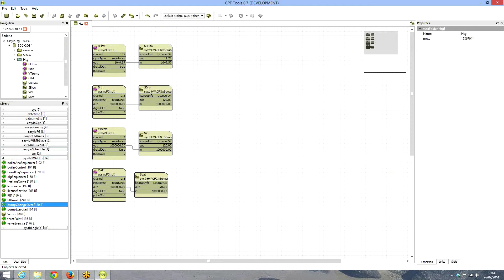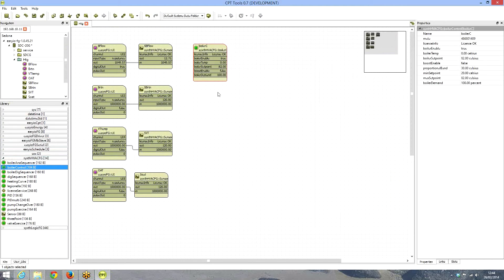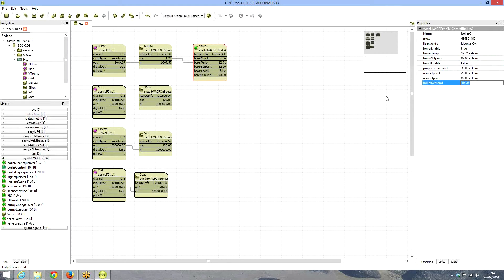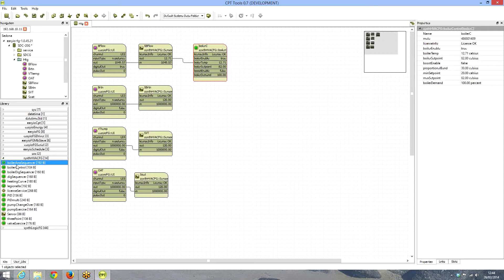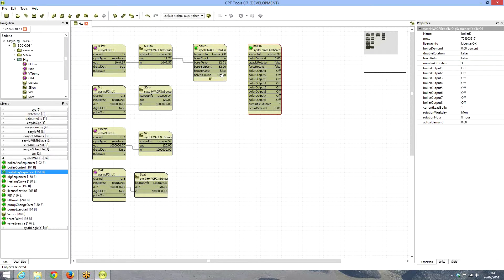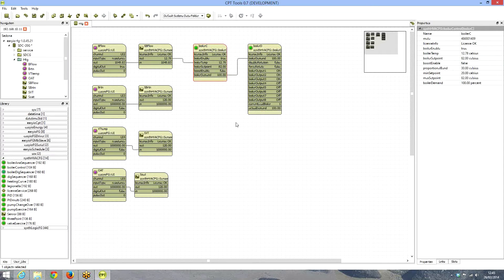First we drag and drop the boiler control object onto the page and link the boiler flow temperature to that boiler temperature input. Highlighting the boiler control object, we can see its properties: boiler temperature, boiler set point, boost enable, proportional band, and boiler demand. We leave most as default. Next, we drag and drop the digital boiler sequencer and link the boiler demand output to the boiler demand input on that digital boiler sequencer.